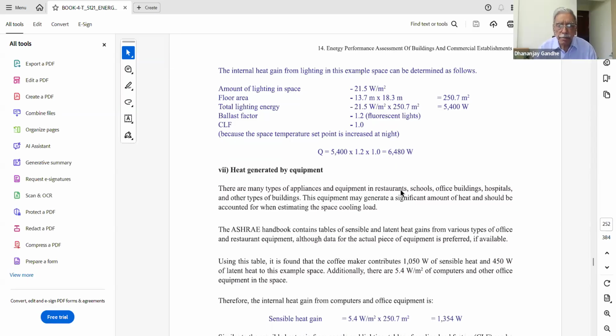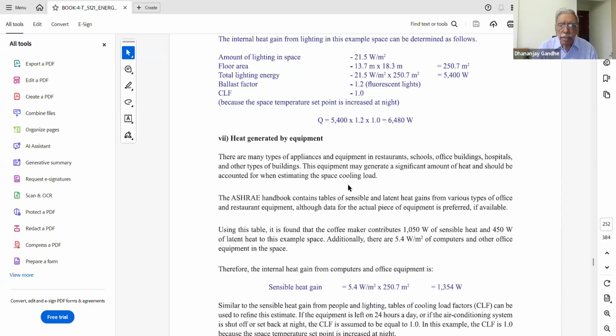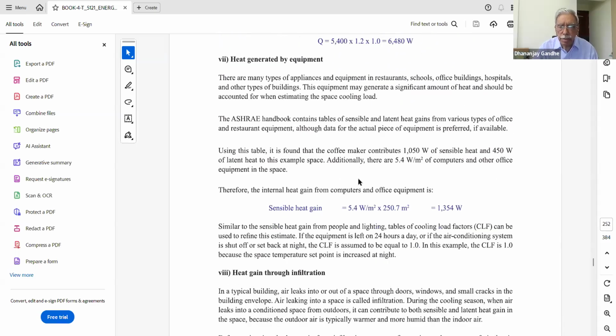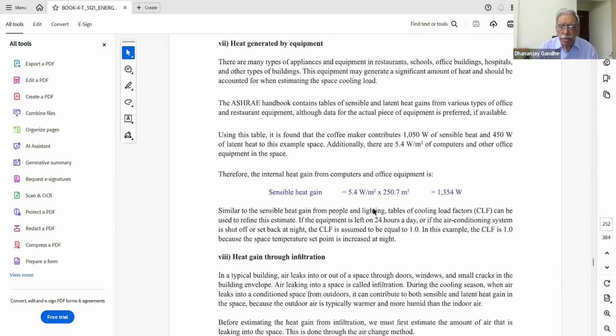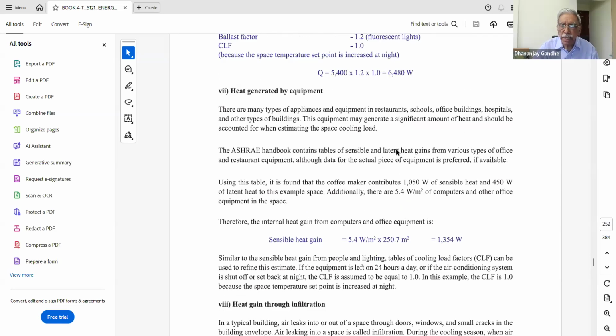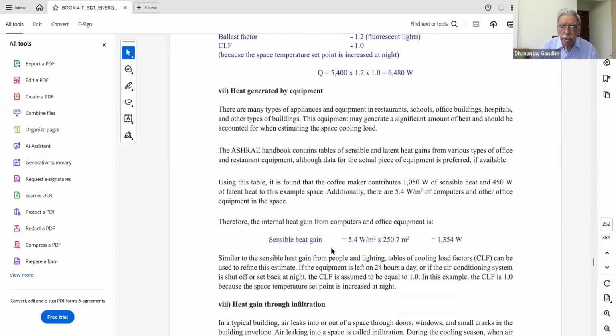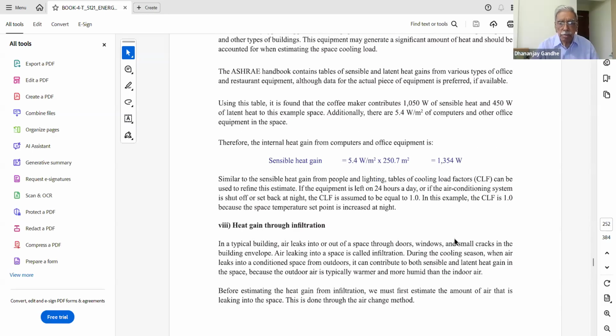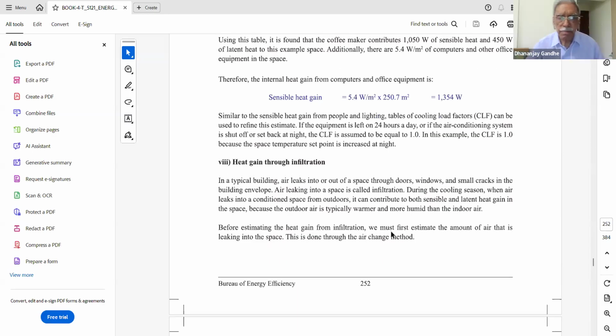So just like lighting, one can also calculate the heat generated by the equipment. For that you will have to know the wattage of that particular equipment. So it is mentioned that for computers and office equipment, the load is 5.4 watts per m square. So you multiply by the area, which is the same as over here. That gives you the sensible heat gain from the equipment. So this is how you calculate for the equipment.